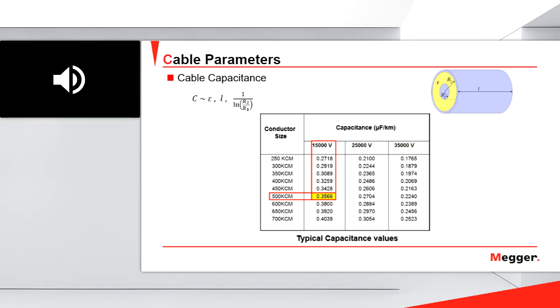So the length of the cable is very important, because if I have very long cables, I will need a bigger thumper or a bigger fault locator. There is a rule of thumb that says the thumper of the fault locator should have at least between 6 and 10 times the capacitance of my cable.